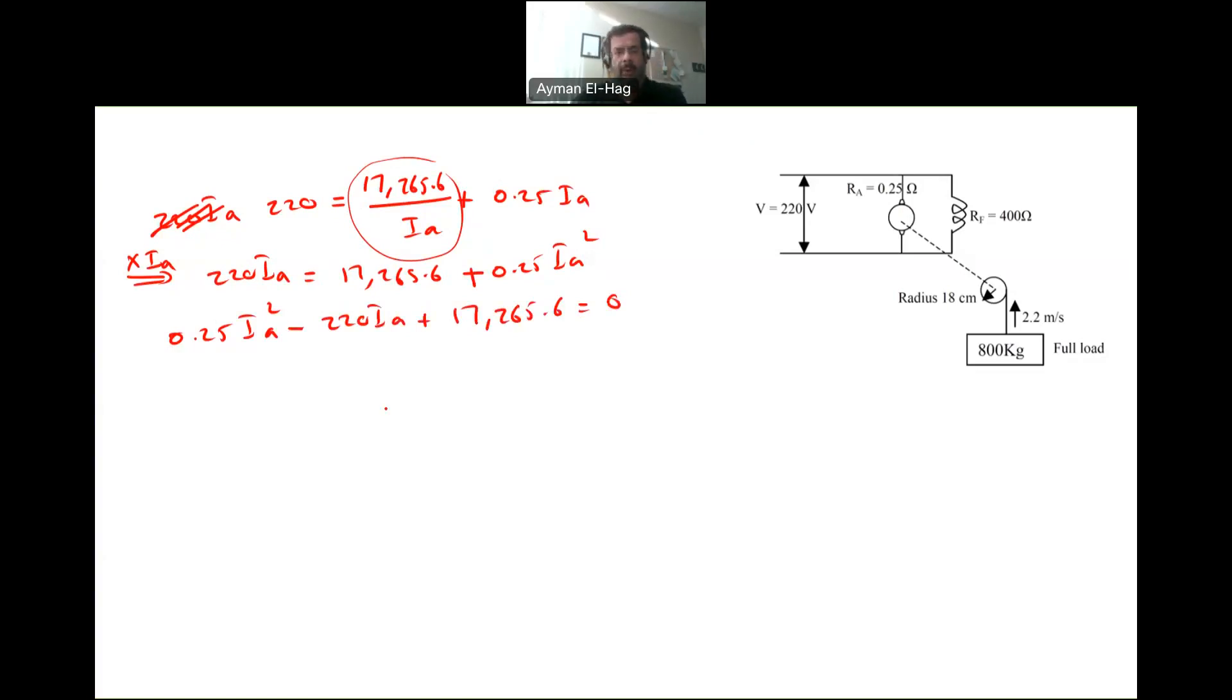Now we need to solve this. You can easily solve this. Your IA solution for a quadratic equation minus B plus minus B squared minus 4AC divided by 2A. So your B is equal to minus 220, your A is equal to 0.25, and your C is equal to 17,265.6. When I substitute and try to solve for this, you will find two solutions: 792.9 amps or 87.1 amps. This is from the math perspective.